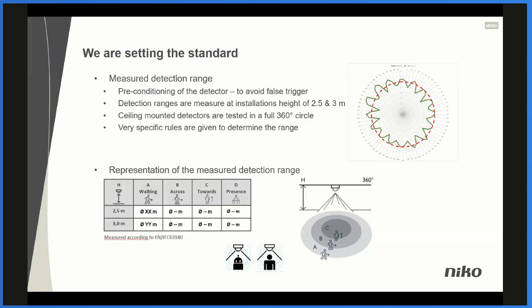And as you can see, the red ring indicates the norm, saying this is the detection range that you can have for this detector. But before, as a supplier, you could go to the even outermost point of the circle, so you could have an even bigger detection range. But then it's not what you see is what you get. This is why this standard is also very good, because everybody needs to be inside a certain specific range in order to have the detection range.